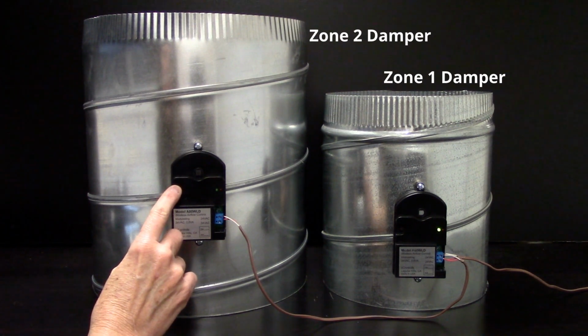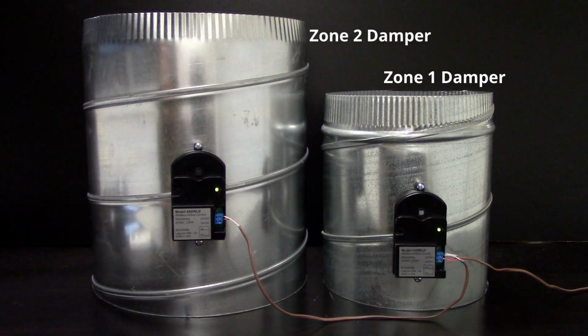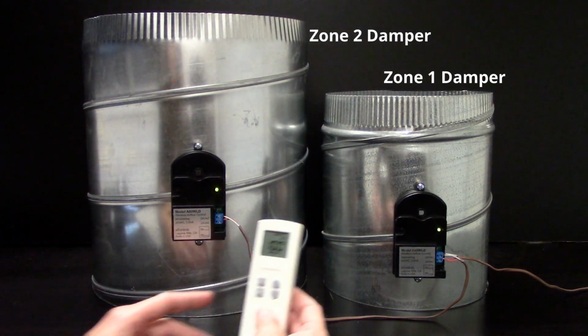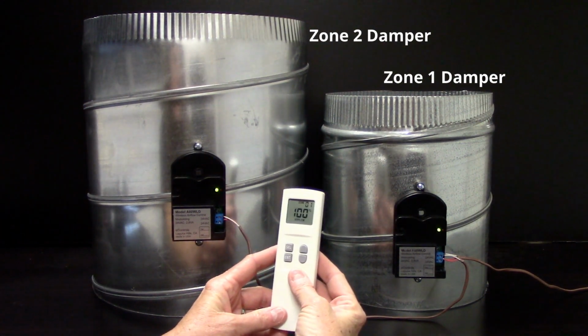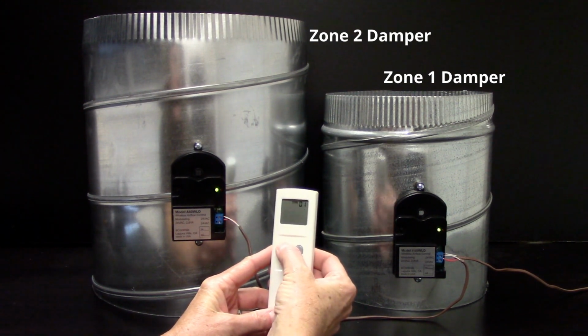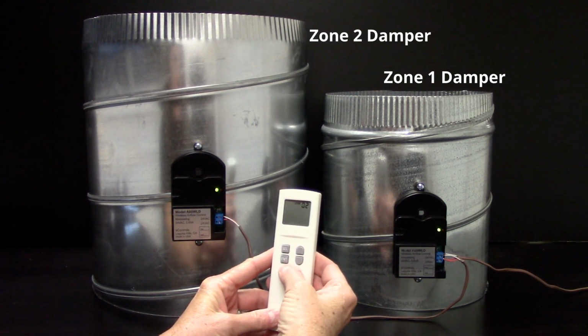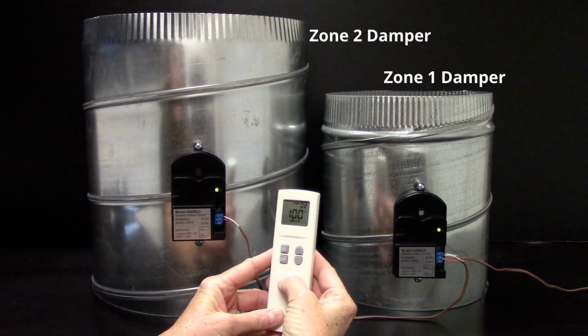We'll set this damper to Zone 2. There is a section in the installation manual and the user manual where you can record the zone location. You can also record the zone number on the actuator. To control Zone 2, you will need to select Zone 2 on the remote. Press the Select key, then use the Up key to select Zone 2, then press Enter.